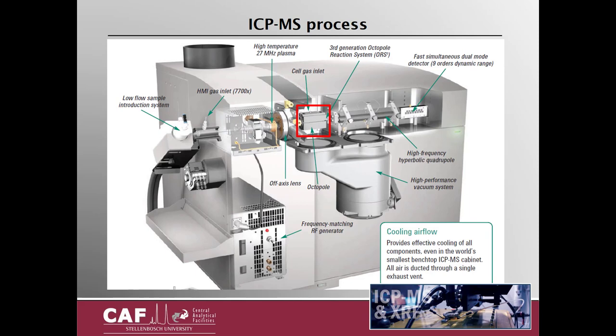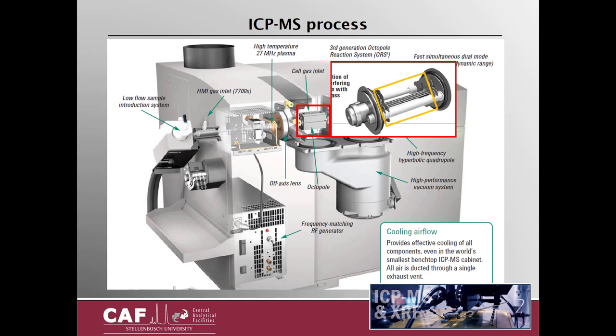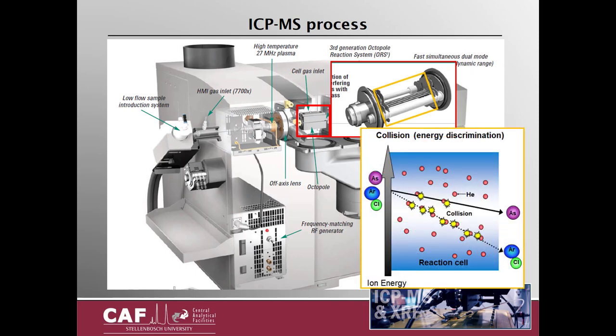In order to remove interferences, ICP-MS has a small cell filled with helium through which all the ions pass. The principle of interference removal is that in a small space pressurized with helium, the larger interference molecules — argon chloride in this example — are 99.9% guaranteed to collide with a helium molecule, which slows them down. The smaller analyte ions, namely arsenic in this example, will collide less with helium and have a higher velocity. The cell barrier then only allows ions at the specific velocity of the analytes to pass, while the slower interferences are stopped. A specific voltage exists for all analytes of interest, so they are sequentially let out of the cell at the time the instrument wants to measure them.